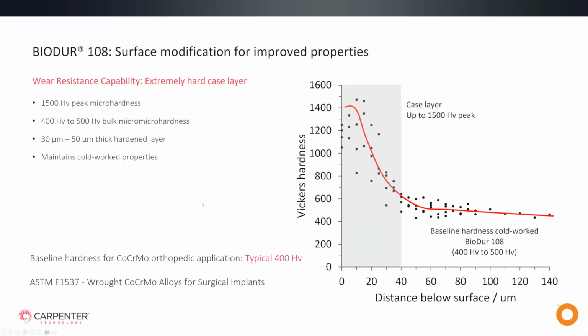However, I think this slide does a bit better job of explaining the material and the potential of the nitriding process. So first, again, the surface nitriding of BioDur 108 is performed at lower temperatures, and this is purposeful, right? It preserves the cold worked microstructure and the underlying strength, the underlying toughness, the grain size, the grain flow. But in doing so, the process creates this thin, hard case skin that's typically 30 plus microns thick, as I mentioned, and has a peak hardness around 1500 Vickers, or again, 70 plus HRC. So this really drives the wear resistance capability much higher, beyond what I shared in the comparison to cobalt chrome, beyond what the material's bulk capability would be, while maintaining that corrosion resistant, ductile, and fatigue properties of the base material.